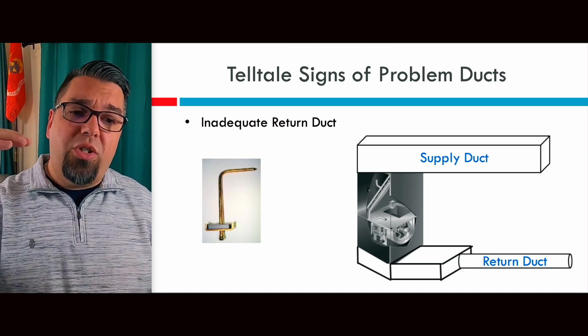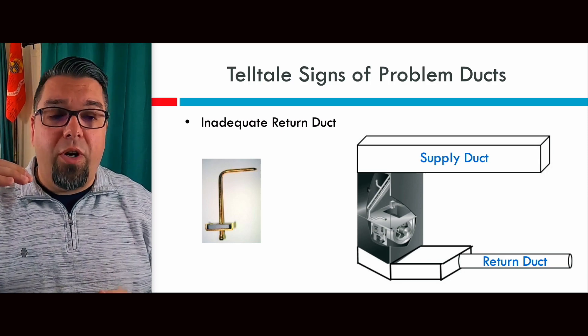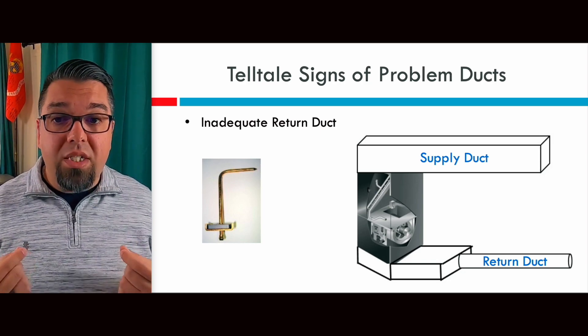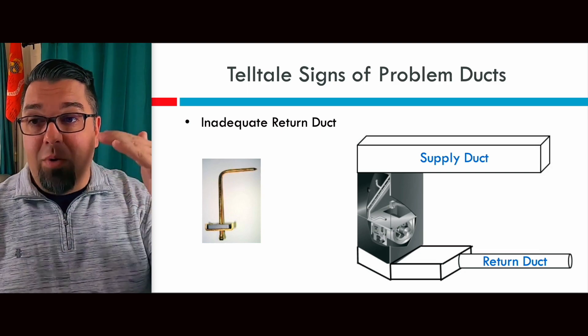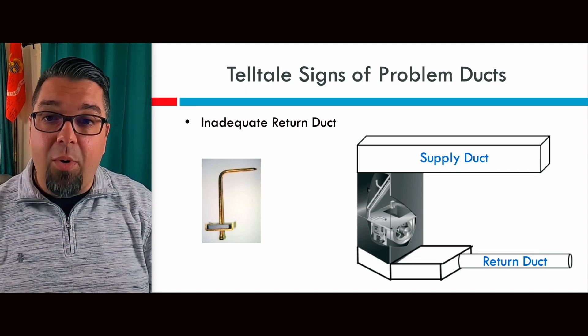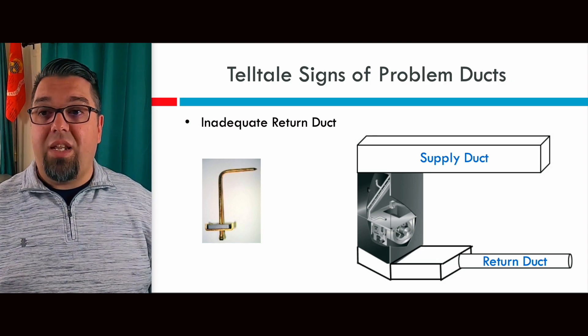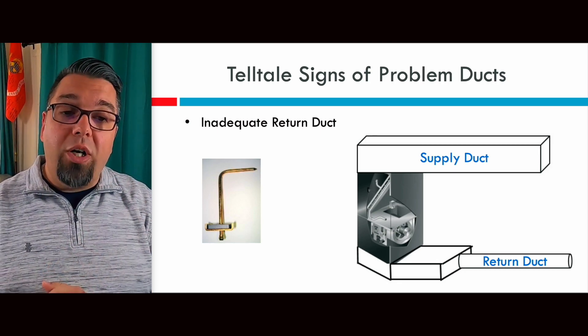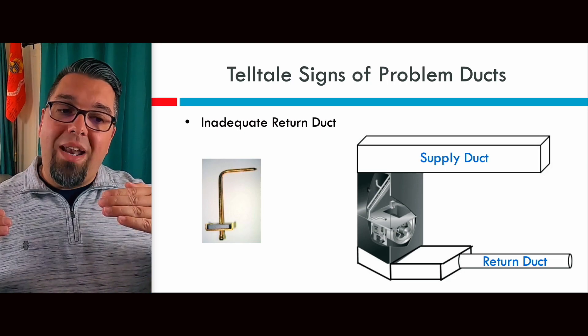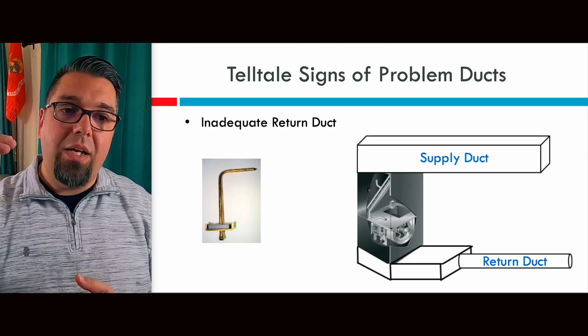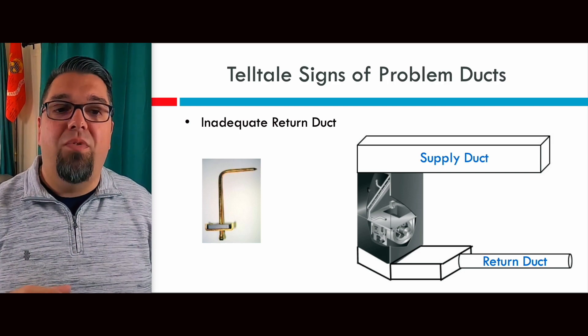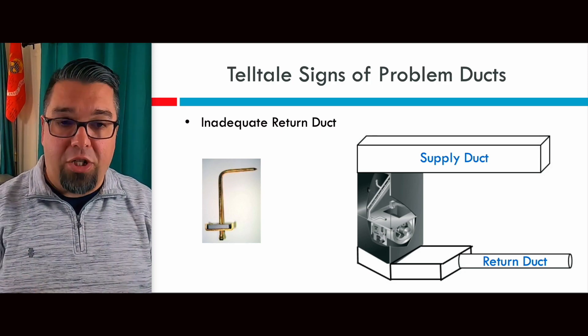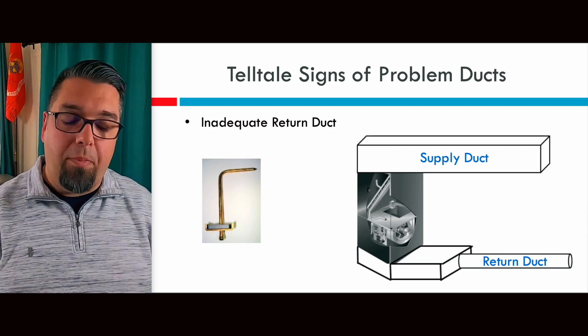If it's just an air handler for a heat pump, you can check the supply duct and get the static pressure there. This should be pretty balanced, and the total static pressure needs to be at the maximum or less. For a PSC style motor, that's probably 0.5 total — so negative 0.25 on the return and positive 0.25 on the supply — that's a balanced duct system. If it's imbalanced, the more negative in the return or the more positive in the supply, you can see which side of the system is inadequate. If the return duct's too small, you'll have a much more negative pressure in the return than the positive pressure in the supply.